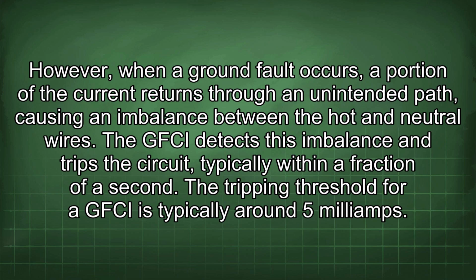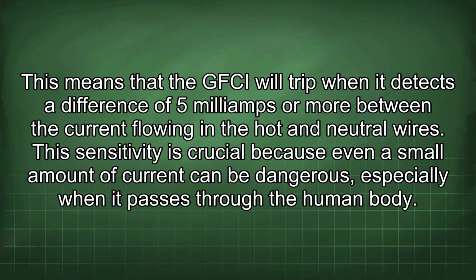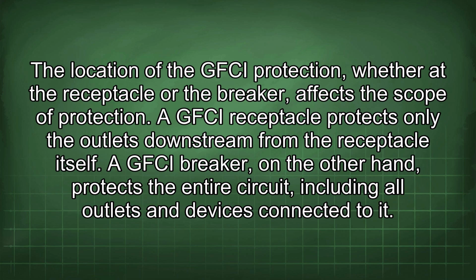The tripping threshold for a GFCI is typically around 5 milliamps. This means that the GFCI will trip when it detects a difference of 5 milliamps or more between the current flowing in the hot and neutral wires. This sensitivity is crucial because even a small amount of current can be dangerous, especially when it passes through the human body. The location of the GFCI protection, whether at the receptacle or the breaker, affects the scope of protection. A GFCI receptacle protects only the outlets downstream from the receptacle itself. A GFCI breaker, on the other hand, protects the entire circuit, including all outlets and devices connected to it.